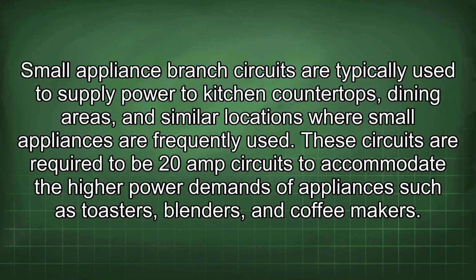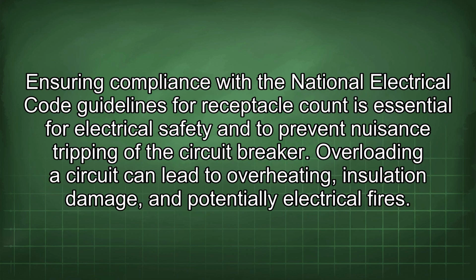Small appliance branch circuits are typically used to supply power to kitchen countertops, dining areas, and similar locations where small appliances are frequently used. These circuits are required to be 20 amp circuits to accommodate the higher power demands of appliances such as toasters, blenders, and coffee makers. Ensuring compliance with the National Electrical Code guidelines for receptacle count is essential for electrical safety and to prevent nuisance tripping of the circuit breaker. Overloading a circuit can lead to overheating, insulation damage, and potentially electrical fires.